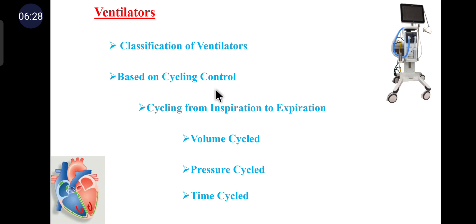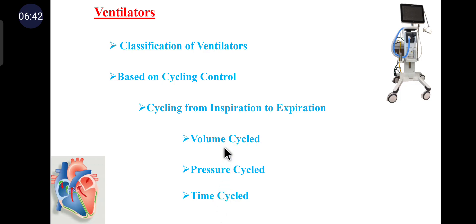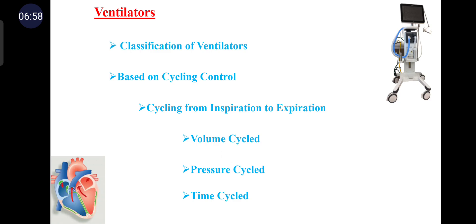Classification based on cycling control: the cycling control determines the change from the inspiratory phase to the expiratory phase and vice versa. For inspiration to expiration, it is based on volume cycle, pressure cycle, and time cycle. In a volume cycle ventilator, the expiratory phase begins after a preset tidal volume has been delivered into the patient circuit. A pressure override valve ensures that if pressure exceeds a predetermined maximum, the ventilator will cycle regardless of whether the set volume has been administered.